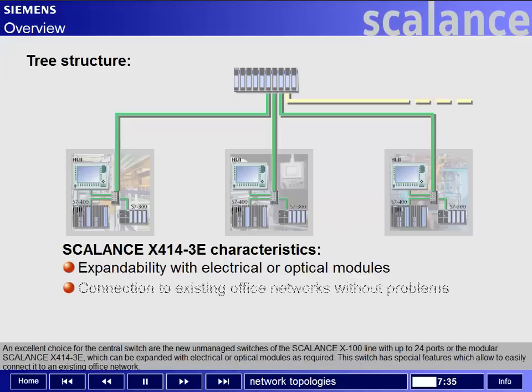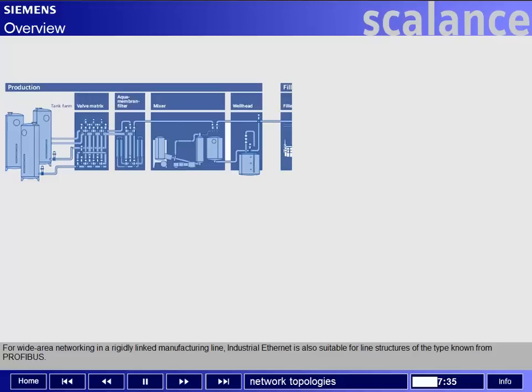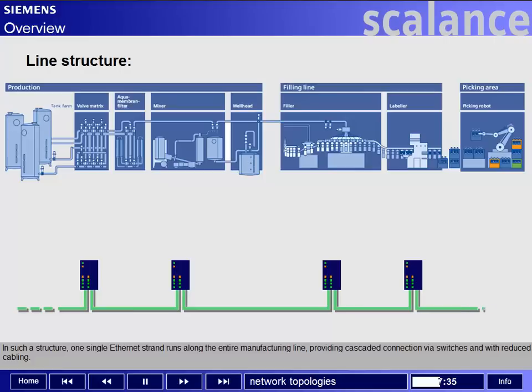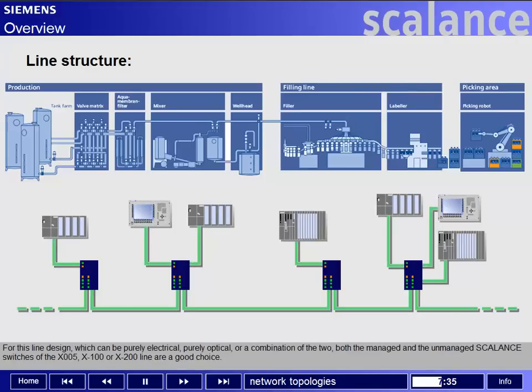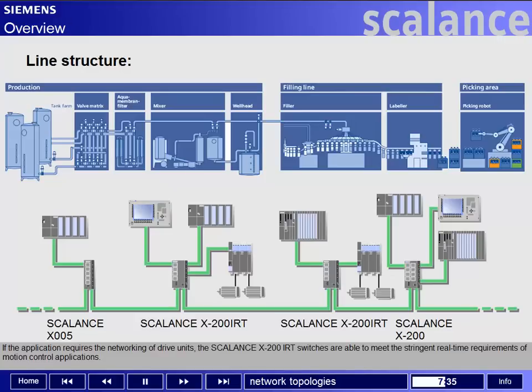For wide-area networking in a rigidly linked manufacturing line, industrial Ethernet is also suitable for line structures of the type known from PROFIBUS. In such a structure, one single Ethernet strand runs along the entire manufacturing line, providing cascaded connection via switches with reduced cabling. The nodal points can connect with single Ethernet stations or with a further star structure. For this line design — which can be purely electrical, purely optical, or a combination of the two — both the managed and the unmanaged Scalance switches of the X005, X100, or X200 line are a good choice. If the application requires the networking of drive units, the Scalance X200 IRT switches are able to meet the stringent real-time requirements of motion control applications.